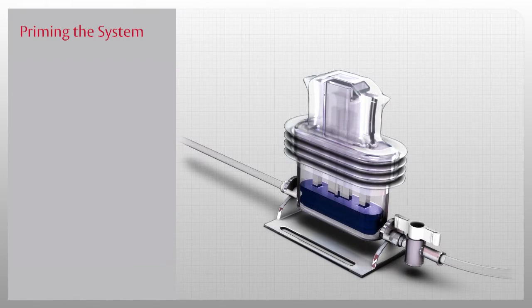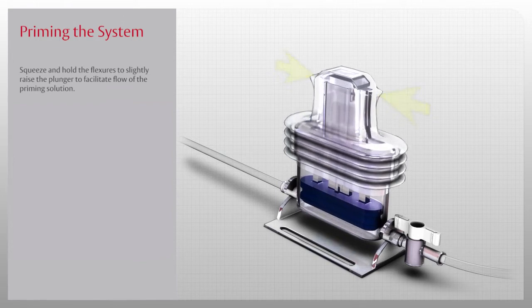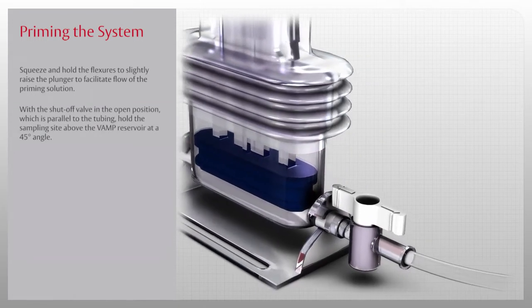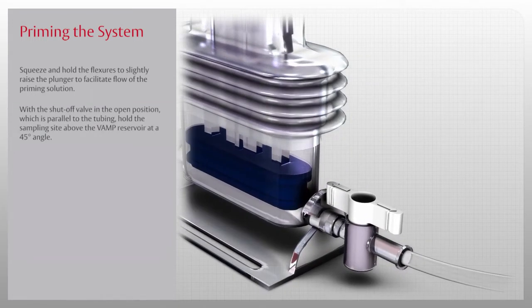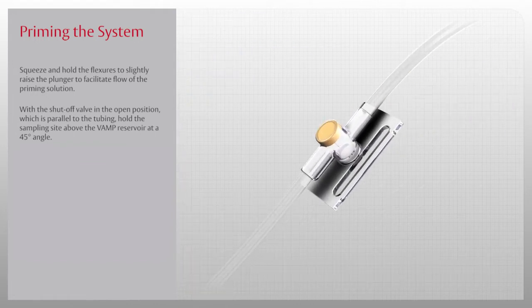Now that you have set up the VAMP Adult System, let's learn how to prepare and use the system. The first step is priming. To begin, first squeeze and hold the flexures to slightly raise the plunger to facilitate flow of the priming solution. Now, with the shutoff valve in the open position, which is parallel to the tubing, hold the sampling site above the VAMP reservoir at a 45-degree angle.